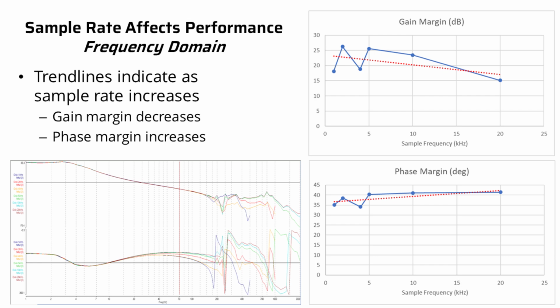So let's look at some real data. I have a servo motor set up with an amplified sine encoder. I have a small disc on it to give it some inertia, so it has a little bit of resonance in it, but not a lot. And what I've done is a series of motions and collected some frequency responses and some time domain responses by varying both the resolution and the sample time, and we can take a little bit of information from that data.